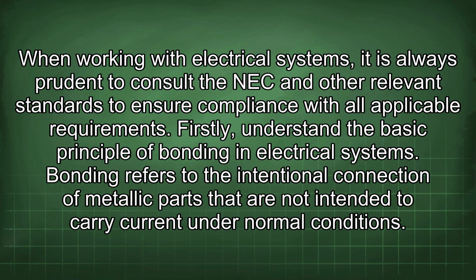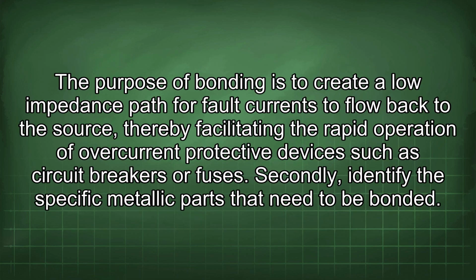When working with electrical systems, it is always prudent to consult the NEC and other relevant standards to ensure compliance with all applicable requirements. Firstly, understand the basic principle of bonding in electrical systems. Bonding refers to the intentional connection of metallic parts that are not intended to carry current under normal conditions. The purpose of bonding is to create a low impedance path for fault currents to flow back to the source, thereby facilitating the rapid operation of overcurrent protective devices such as circuit breakers or fuses.